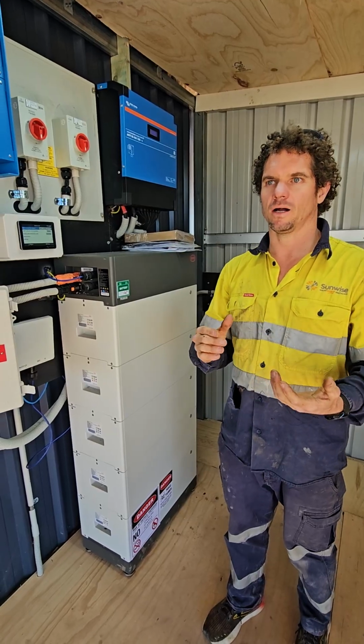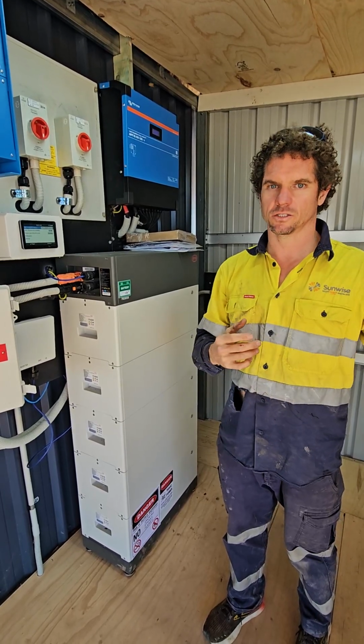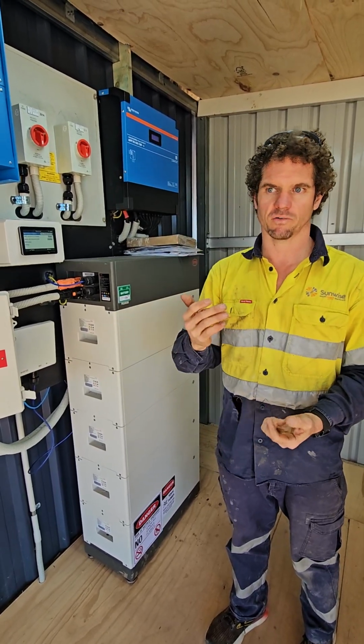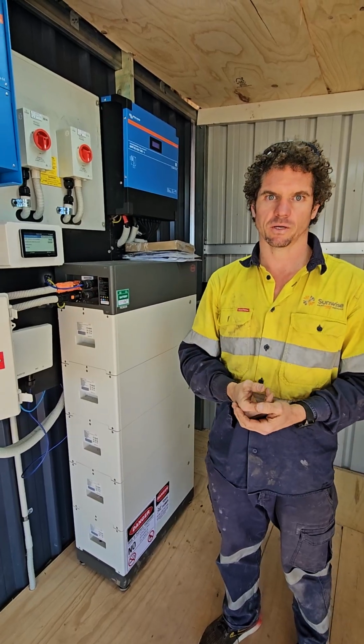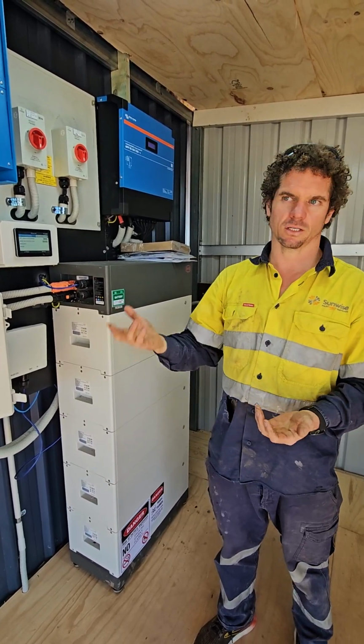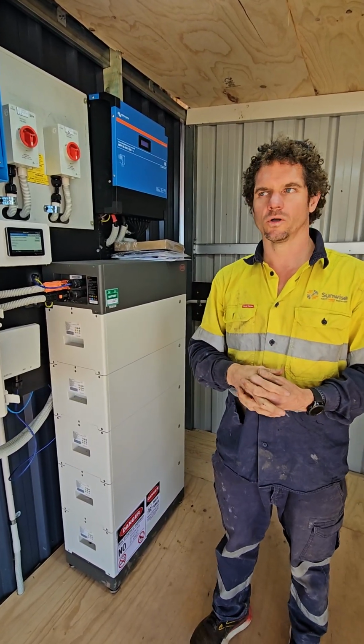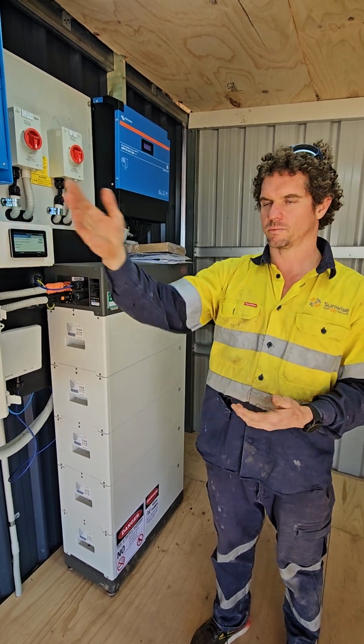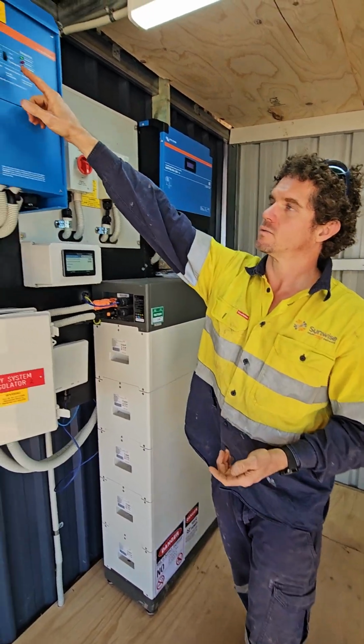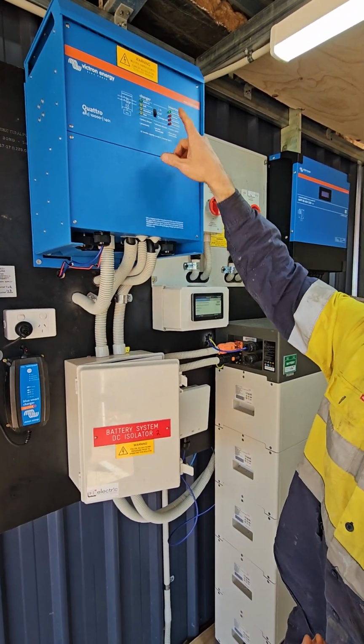That will allow the battery to get some charge straight from the generator to top itself up before you turn all your loads back on with the system. Once the battery gets up to around 20% or more, you can turn all the loads back on at the switchboard, flick that switch back up to the on position, and you'll be away again.